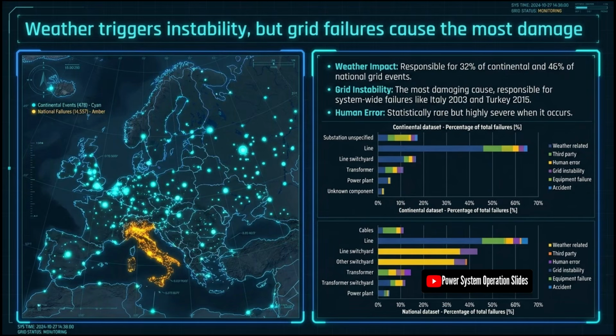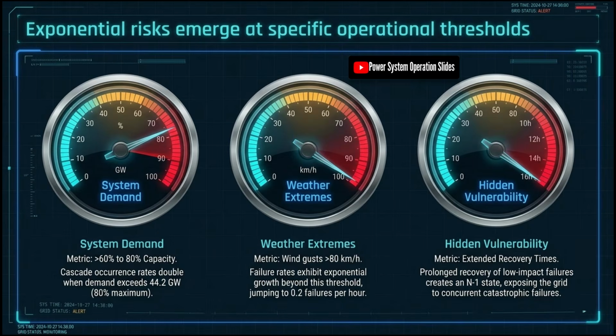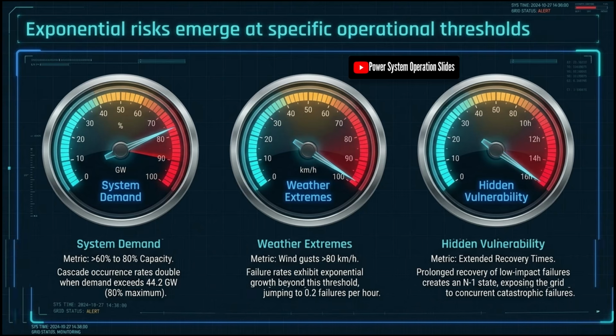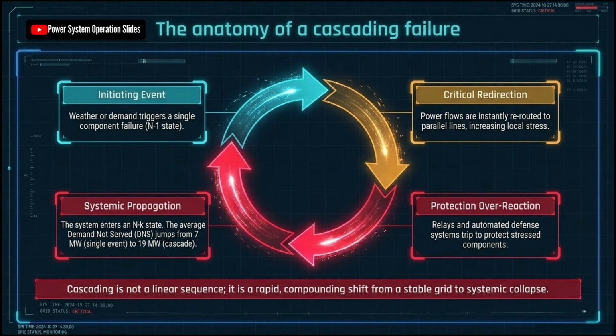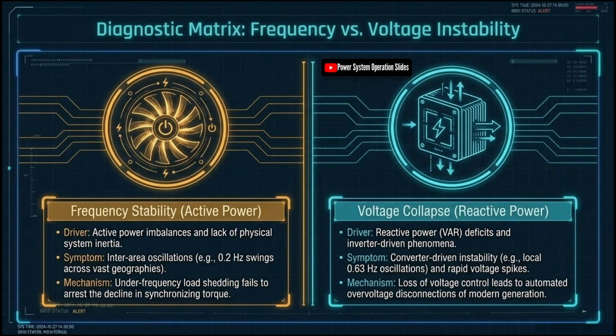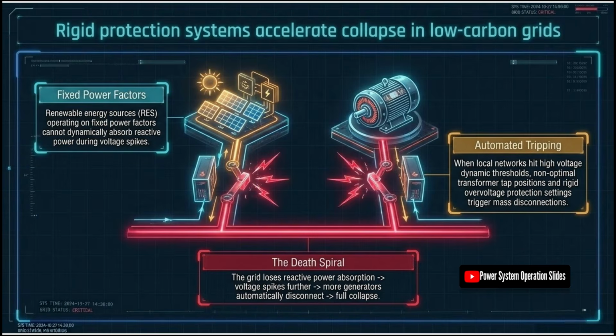Preventing major blackouts therefore requires a transition from conventional static security assessment toward continuous, dynamic, and wide area assessment. Modern utilities and TSOs increasingly rely on phasor measurement units, wide area monitoring systems, energy management systems, dynamic security assessment, online contingency analysis, oscillation monitoring, and advanced voltage stability assessment. These technologies allow operators to identify abnormal system conditions before they develop into uncontrollable events. Adequate transmission capacity, reactive power reserves, synchronous condensers, STATCOMs, SVCs, FACTS, HVDC systems, energy storage, and appropriate protection coordination are also essential components of system resilience.